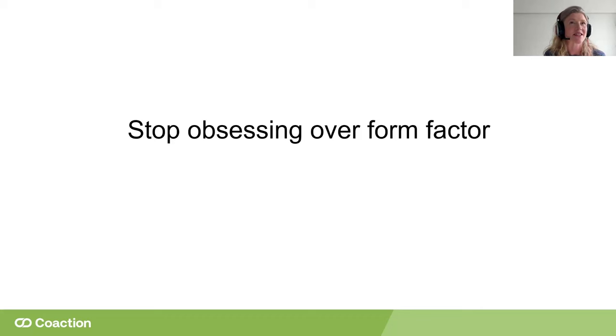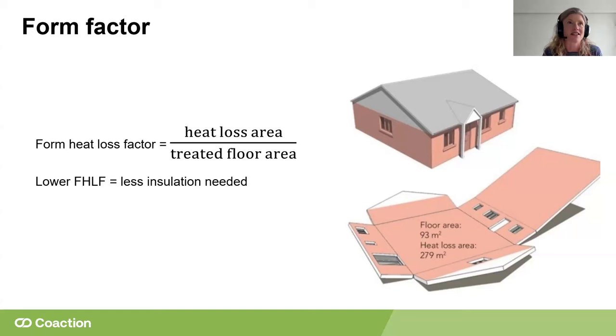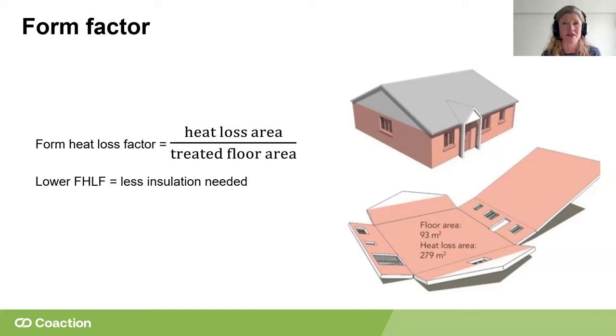Stop obsessing over form factor. We get an awful lot of this on passive house projects. For those who haven't come across it before, it's a metric to give us an understanding of how efficient a design is. The heat loss of a building is a function of its surface area — walls, roof, and floor. We express this as that surface area divided by the treated floor area: the heat loss area is what we pay for, the treated floor area is what we want.